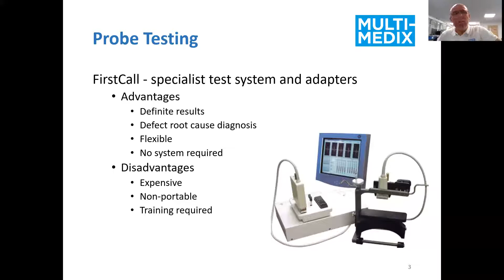So what does it do? There's the first question. Well, what it does is two different tests. The first one is what most of us focus on, and this involves us placing the probe into our target, aligning the probes to the target to get maximum receive. And this target is placed into a water bath where we're going to send an electronic pulse into our transducer array. We're going to transmit, which is going to convert the energy into an acoustic wave. It's going to bounce off our target, and we're going to get a received signal back, which is going to transfer back into electronics. And our FirstCall system is going to record that and give us some key information about the performance of our array and its individual elements.